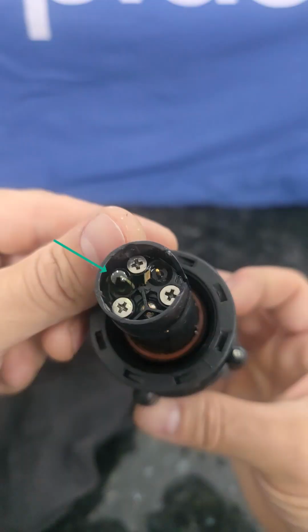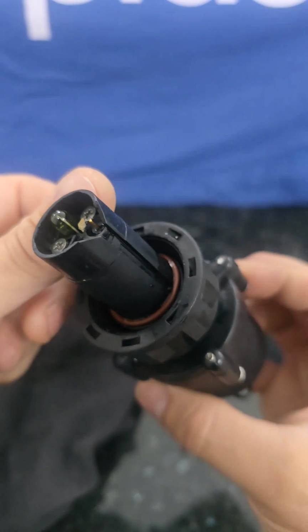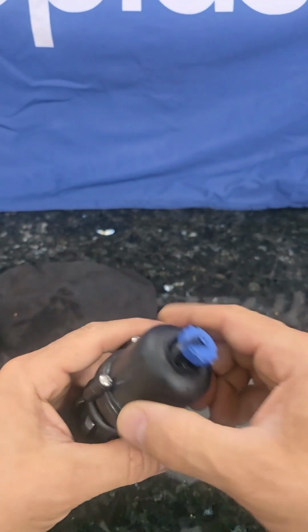Lastly, do a quick inspection of the glass pH probe, gold ORP probe, and stainless steel temperature sensor, and make sure they are all clean and free from any dirt and grime. If needed, repeat the steps above until clean. Once complete, we can now refit the multi-probe.